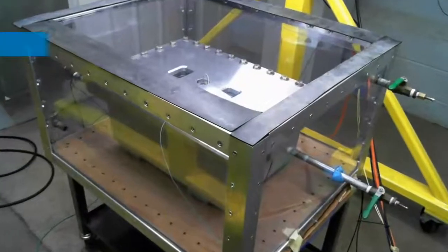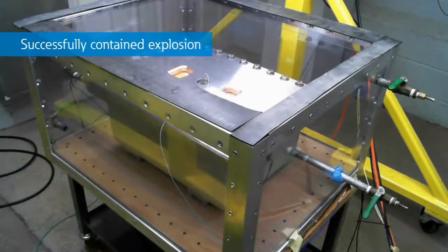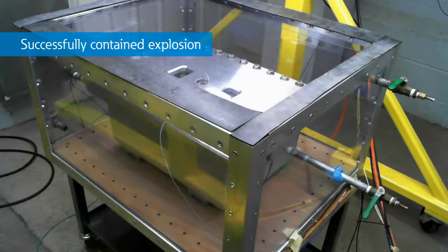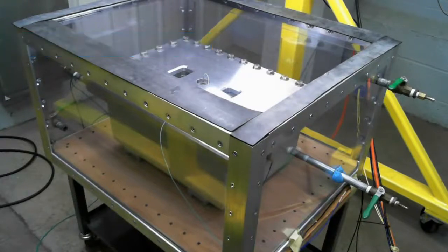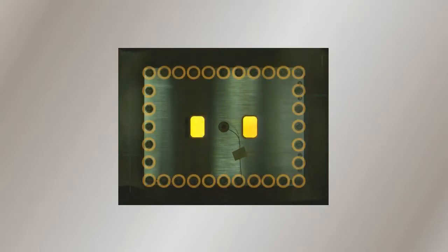NEMA 7 enclosure successfully containing an internal combustion, cooling the explosive gases and preventing the outside hazardous atmosphere from igniting. Watch again in slow motion as the enclosure withstands the combustion forces and cools the explosive gas by diverting it through all the engineered flame paths.